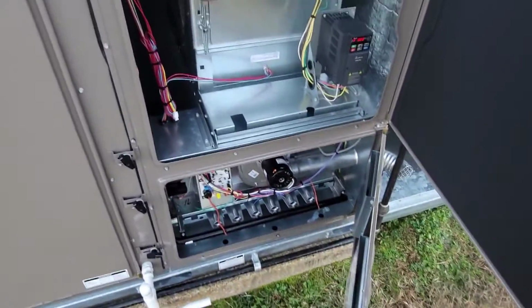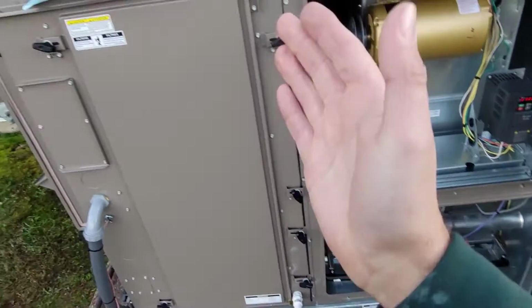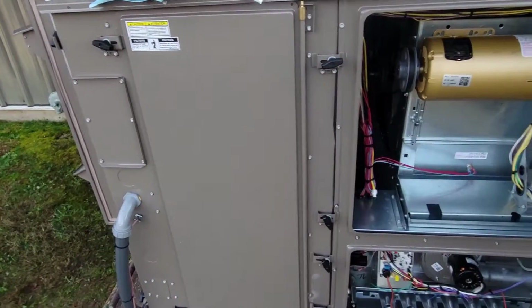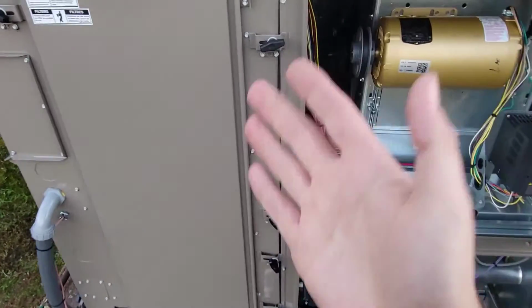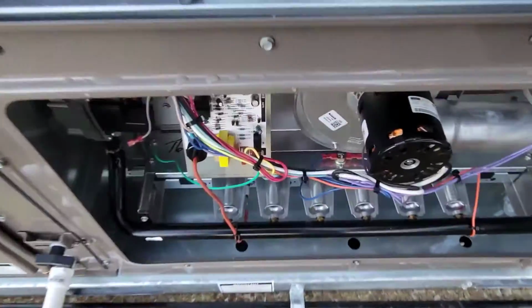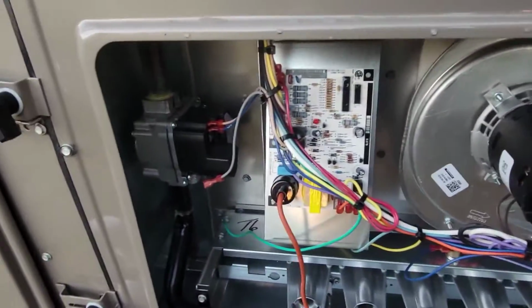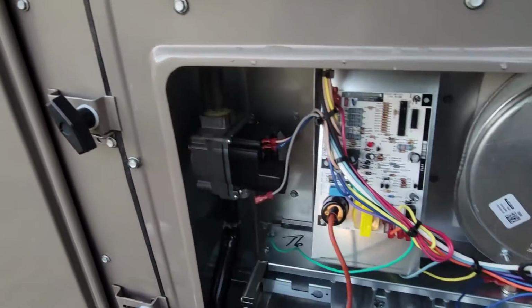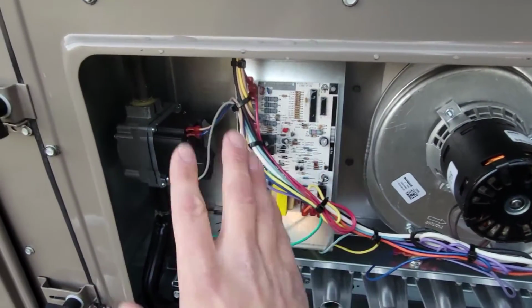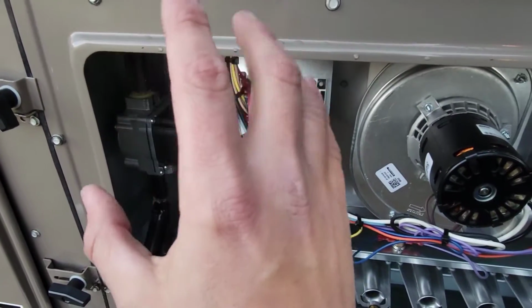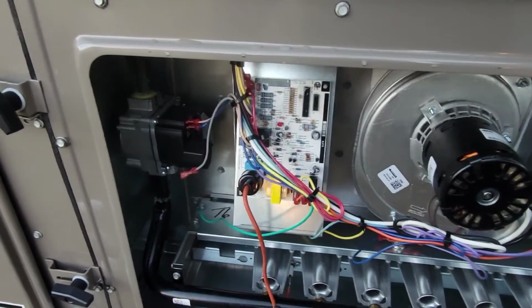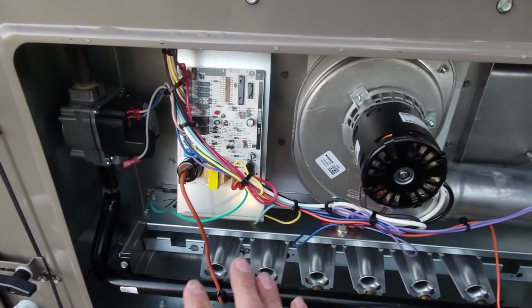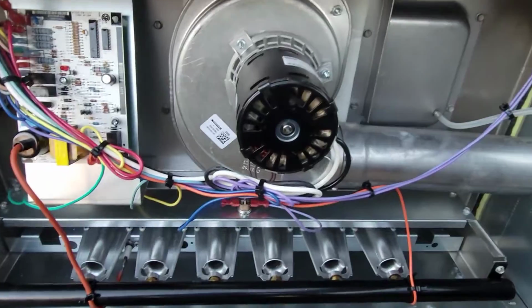You need to make sure that upon commissioning, you not only check the pressures and make sure you don't have low suction pressure or high head pressure or any issues with the pressures. You need to make sure you set the gas pressure. And if you don't know how to do that, you definitely need to check out my playlist. I've got a video on how to use a manometer, setting gas pressure, and how much natural gas and propane burns at. I got a good video on that, so make sure you check that out, okay?